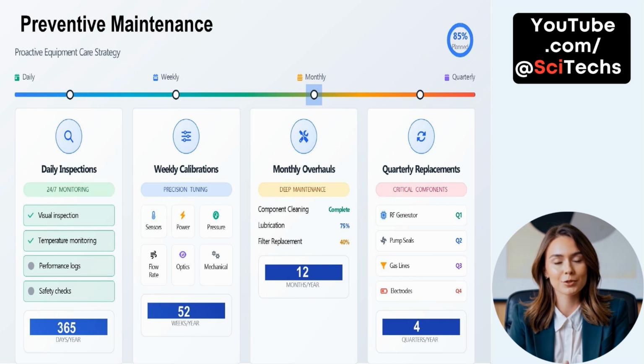Quarterly replacements address critical components like RF generators in Q1, pump seals in Q2, gas lines in Q3, and electrodes in Q4. Altogether, this planned schedule covers 85% of maintenance needs, reducing risk of unplanned downtime while maximizing uptime, performance, and the lifespan of critical assets.